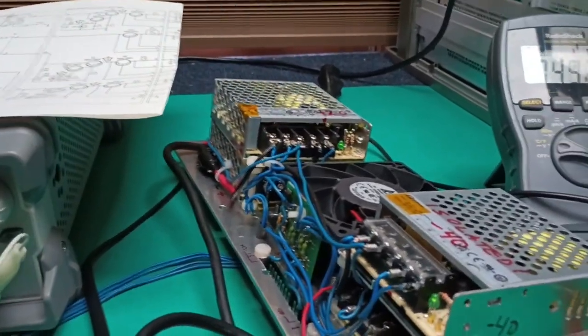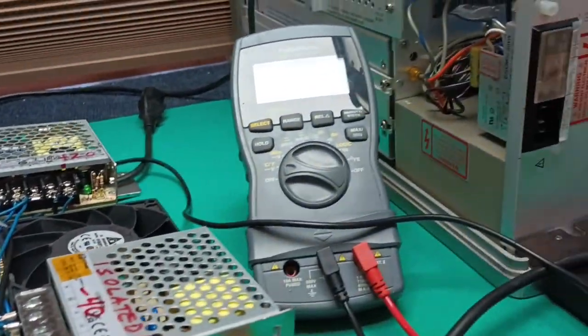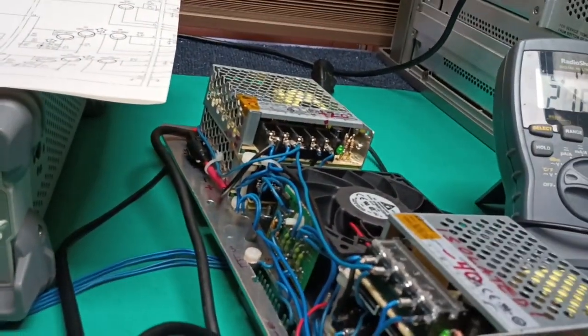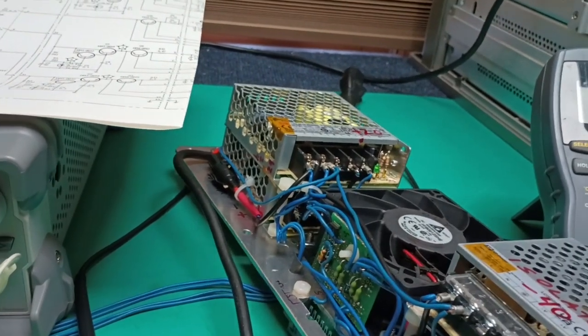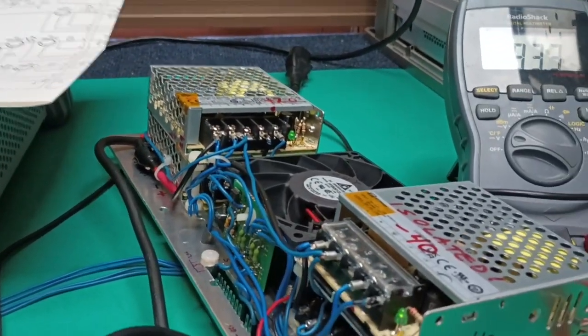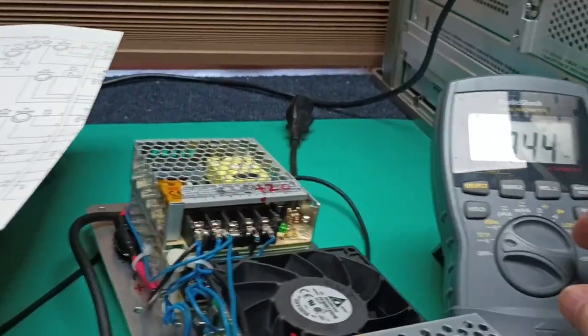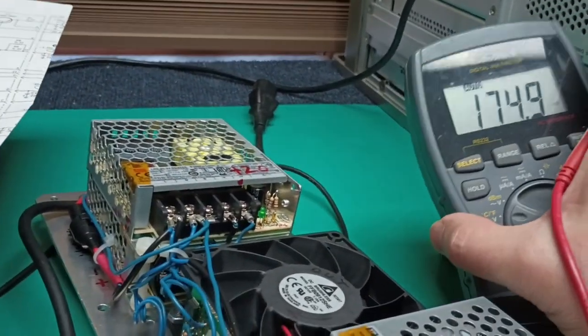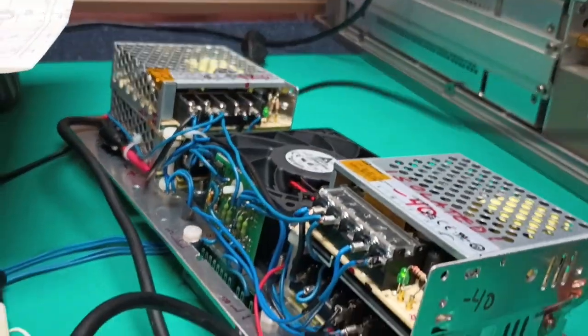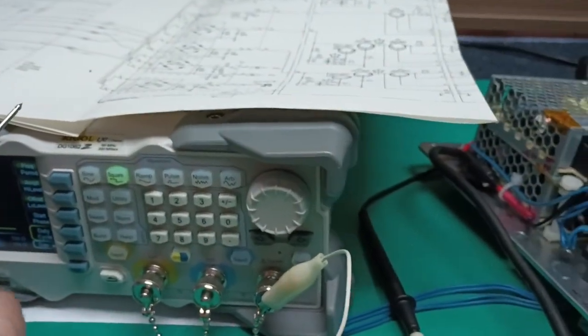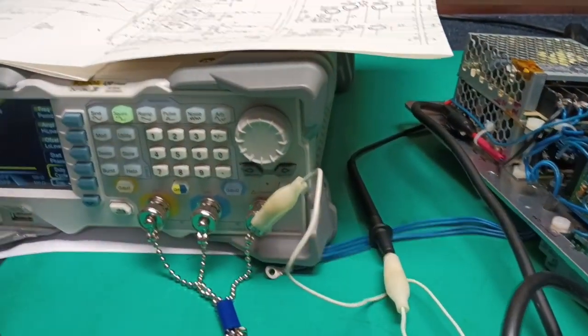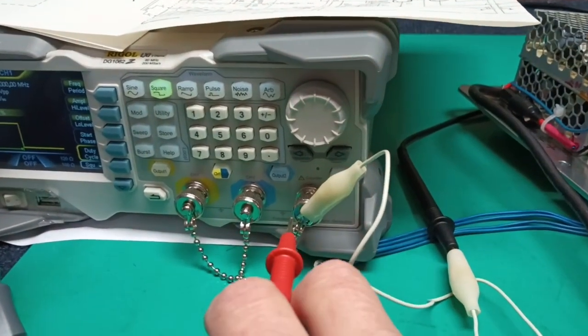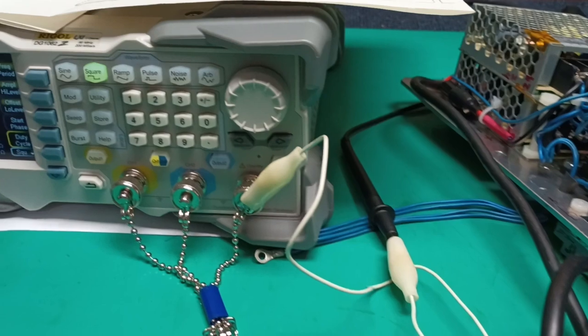So I'm going to plug in this assembly here. I see it's already plugged in. This is a disconnected fan and 4 power supplies: plus 5, plus 20, minus 40, and minus 10. And with the handy dandy meter, we're going to measure the voltages across these two pieces of equipment. And the meter is already commoned to this piece of equipment.